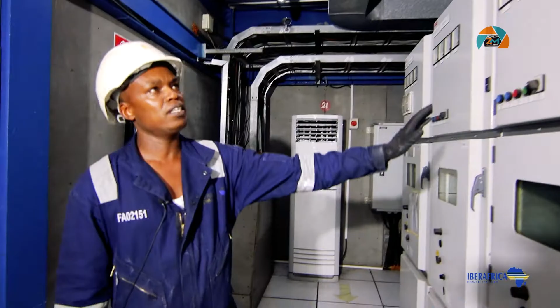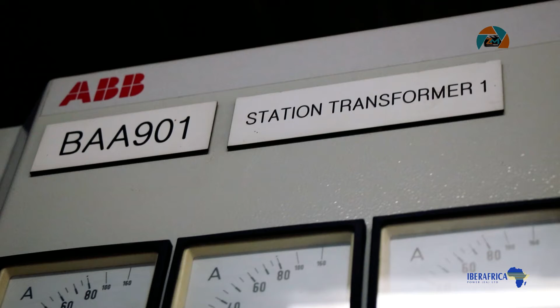After the power comes to this section, we have an outgoing feeder, which also has a circuit breaker, which takes the power to our substation, which has an outgoing transformer, which steps up the power from 11,000 volts to 66,000 volts. The same happens on the other side between G25 and G27.